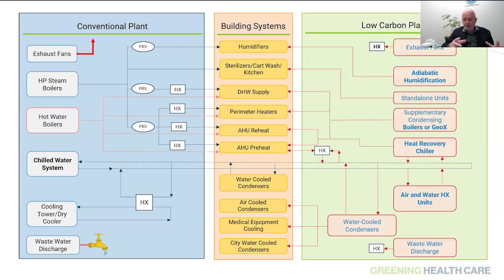If we go across to the conventional plant, this is traditionally how we've done things, primarily with steam. Today, the world looks quite different. We've got heat recovery on exhaust air. We will have heat recovery on discharge wastewater leaving the hospital. Two of the areas we want to focus on today: adiabatic humidification, which we think is going to replace low pressure steam as the approach to humidifying, one of the remaining large steam loads within the facility. And heat recovery chillers, which in most cases will tap into that chilled water distribution system, that transporter that's carrying heat around the hospital, and pump it up to a grade where we can use it to heat the hospital.